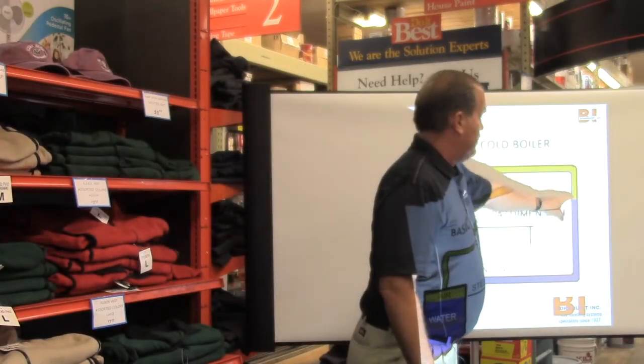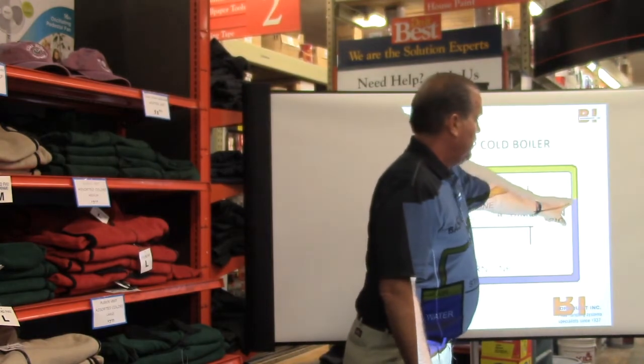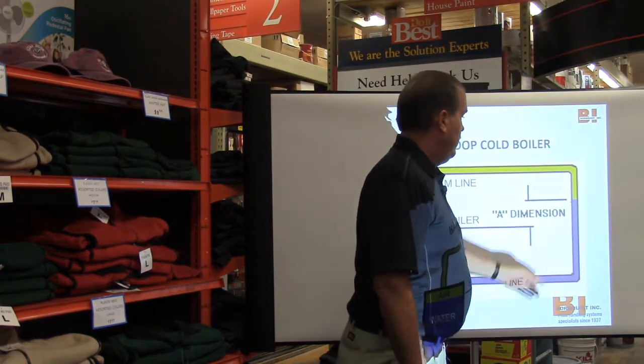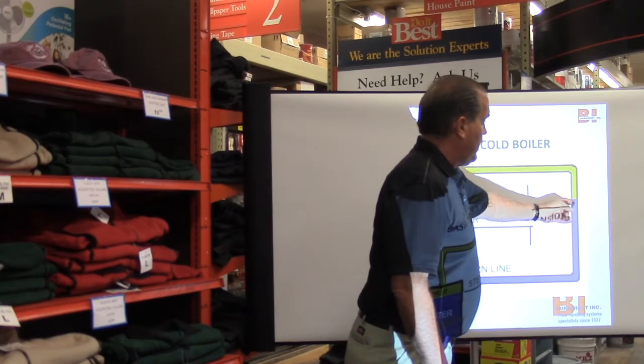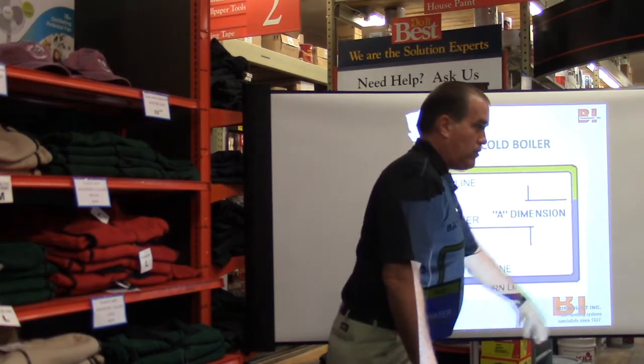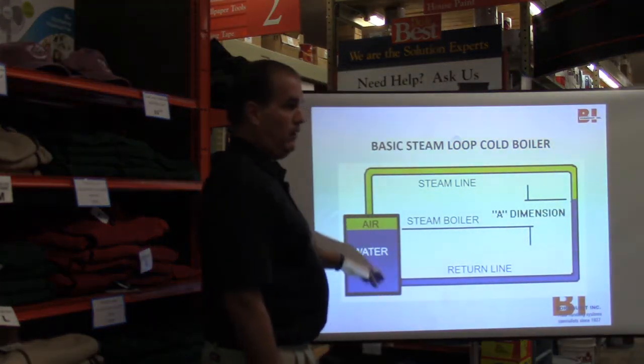If you don't have this dimension properly sized, and they size it by the way they pipe it, what it does is as this condensate picks up, it creates pressure that allows the water to get pushed down and pushes the water level up.